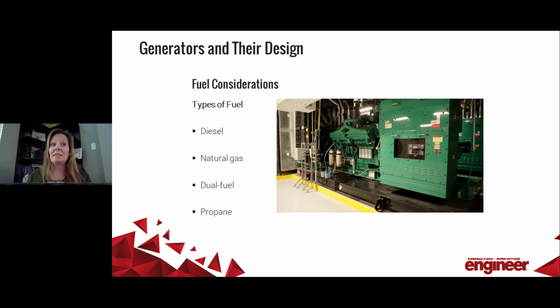So natural gas is actually one of the most efficient fuel types when it comes to generators. The advantages include, you can consider it an unlimited supply because you're connected to your utility company. And depending on the area, it's typically considered a very reliable fuel source as well. And as I mentioned, it's much cleaner burning than diesel. Disadvantages, though, is that historically it's double or triple the first cost of their diesel partners.